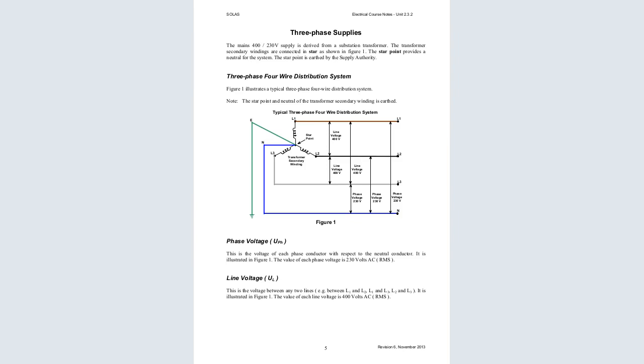So we are still in three-phase wiring. In three-phase wiring, as we said last week, we have two types of wiring. We have a 3-wire and a 4-wire. We said when it's a 4-wire, it means that we are going to tap the red, the yellow, the blue, the three phases plus the neutral. So it will be star connected. It will form something like a star.